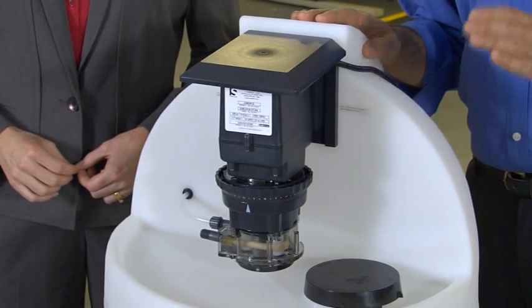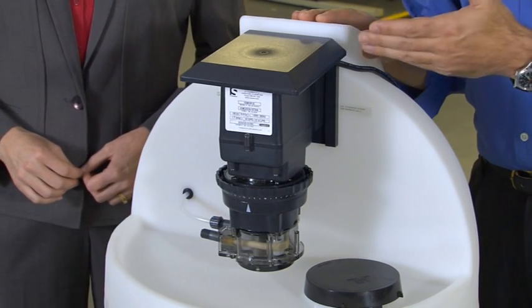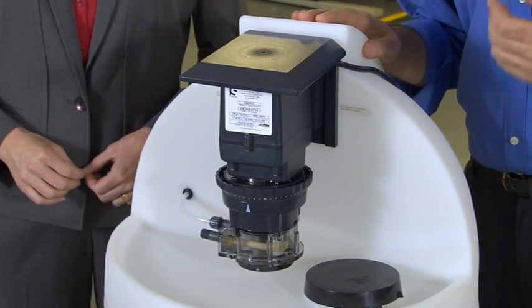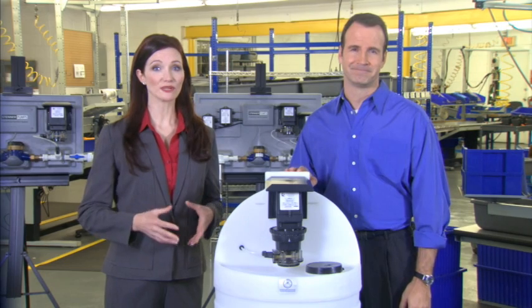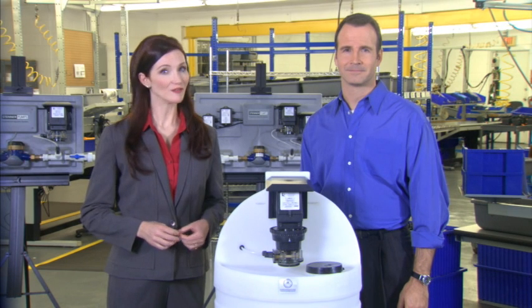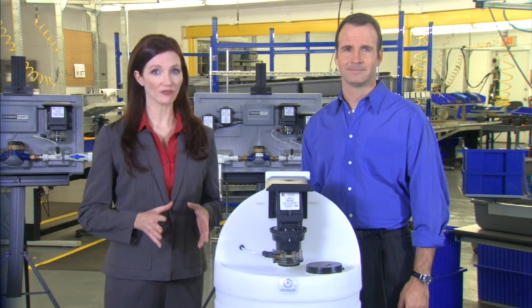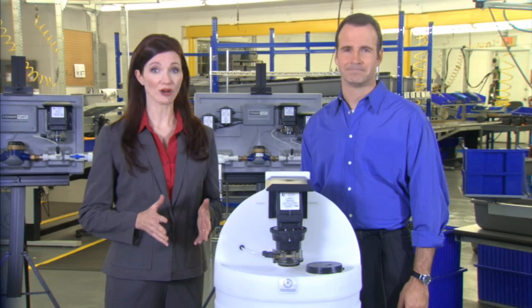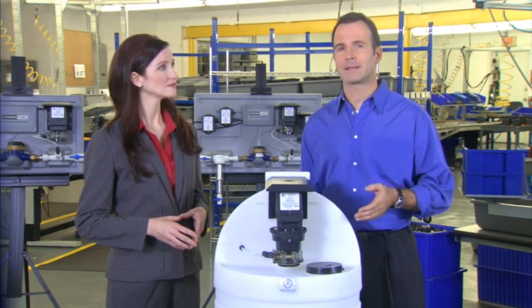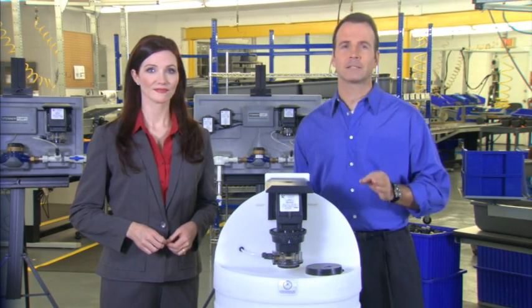The vertical mount with Stenner's mounting bracket allows the rain roof to be installed for use in outdoor or wet environments. Since the motor is fan-cooled, it needs proper ventilation and protection, which is why the rain roof is installed. The motor won't be able to rotate freely if the coil, rotor, and bearings are rusted or corroded. As for wear, cracked or broken bearing brackets can cause the rotor to misalign and bind to the magnetic coil. And of course, the motor voltage must match the power supply to avoid a burned coil.